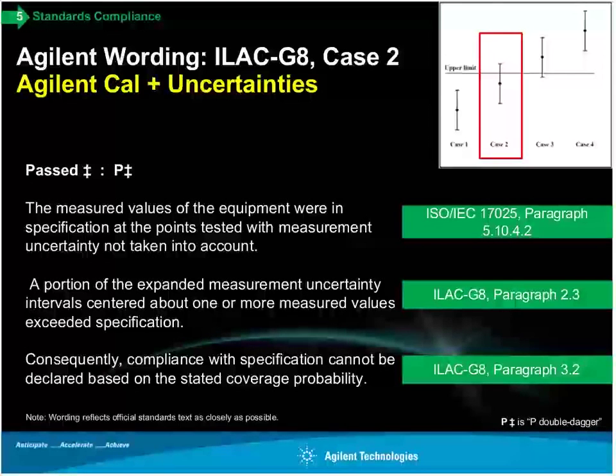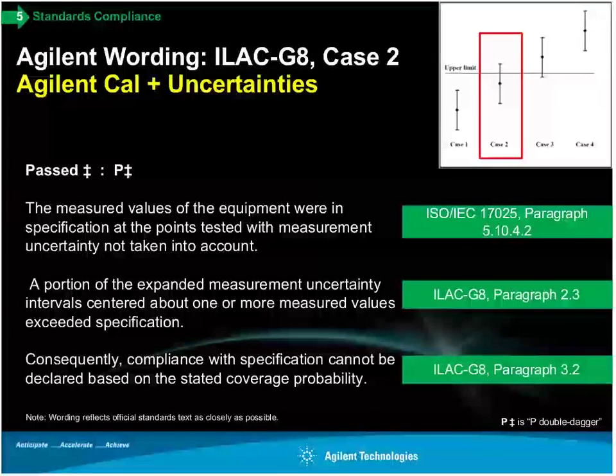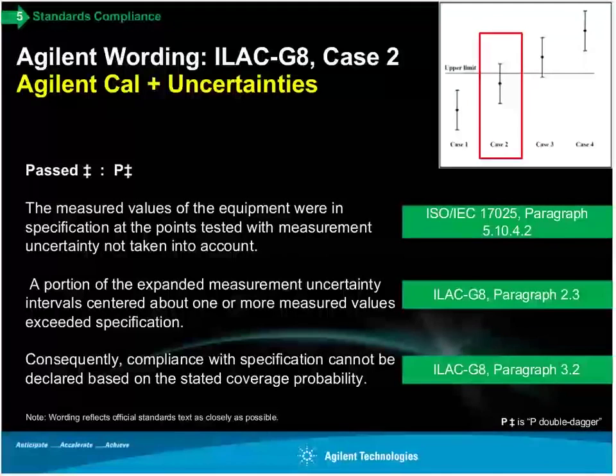Nevertheless, where a piece of equipment's claimed uncertainty or claimed accuracy capability is not much different from that claimed by the laboratory, then you should be rather worried about that, because the chances are that you'll end up with compliance more likely than not, or fail more likely than not. One of the things that's in G8 that's very important is that accredited laboratories must inform their customer of the pass-fail conditions.